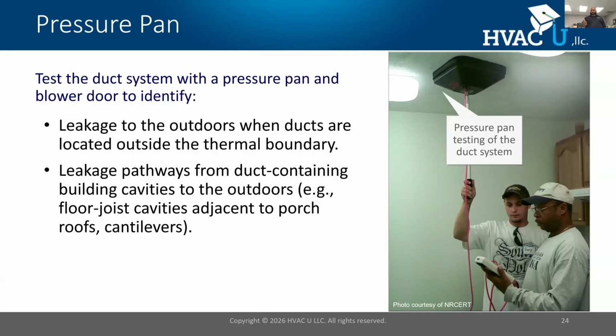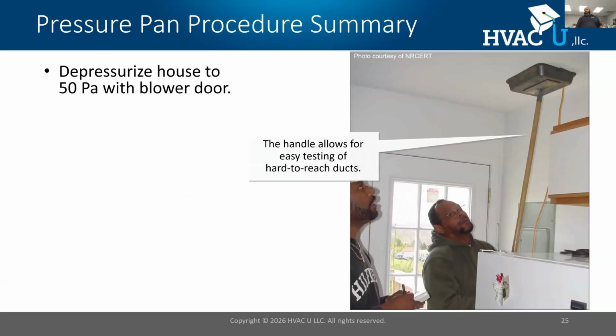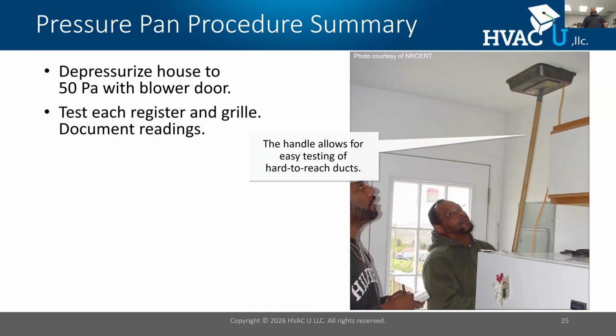The duct system, if designed right, being properly sized and sealed, should be at the same pressure as the house. So I really shouldn't get a large pressure difference. However, if it is leaking, it's connected some portions outside. When I run a blower door test, I will see a difference. All right. So the duct pressure pan test, when I take that pressure pan and I go across a register or grill, helps me to know that the ducts are communicating through the building shell. All right, again, this has to be done with the blower door running. We're using a blower door to maintain that 50 pascals test pressure. And what we're doing, we're using that reference pressure to see if there is any kind of measurable leakage across that duct system.